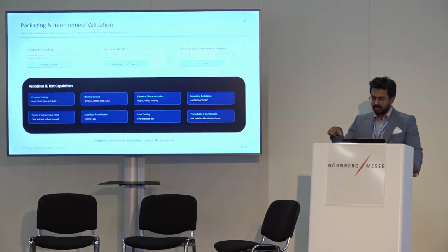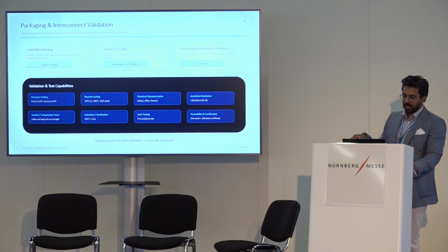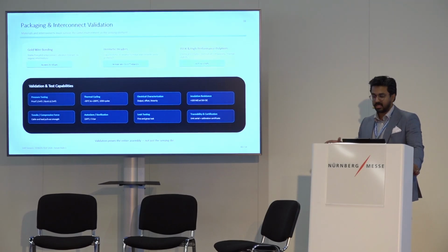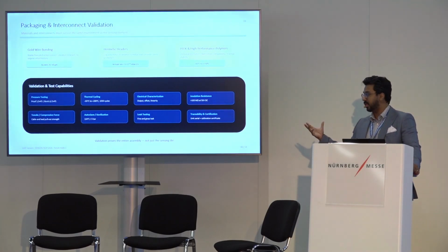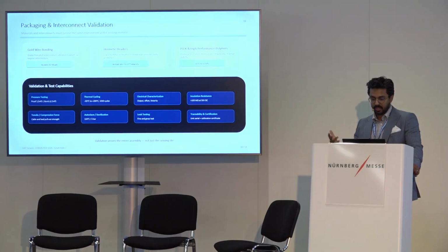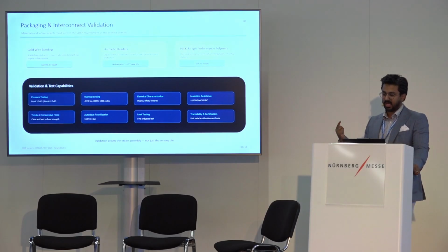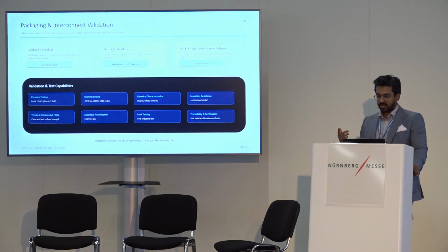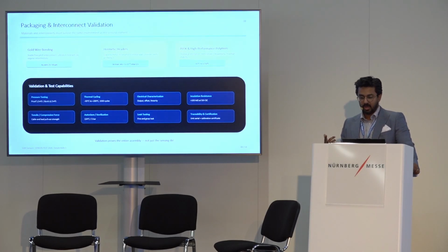And on the bottom stack, what you're seeing are some of the validation and test capabilities that we perform, so we make the sensors as robust as possible. Right, we do thermal cycling, we do electrical characterizations, insulation resistance, autoclavability when relevant, leak testing. One we do is helium testing, or inert gas testing, full traceability.